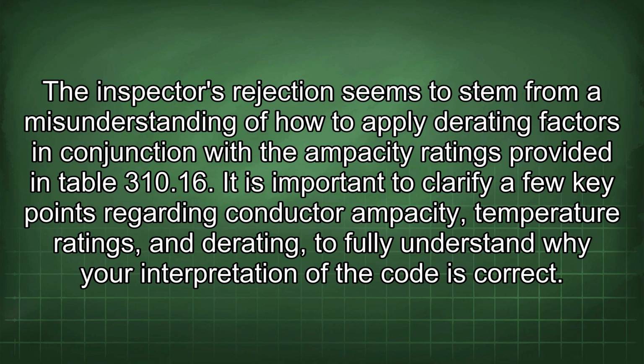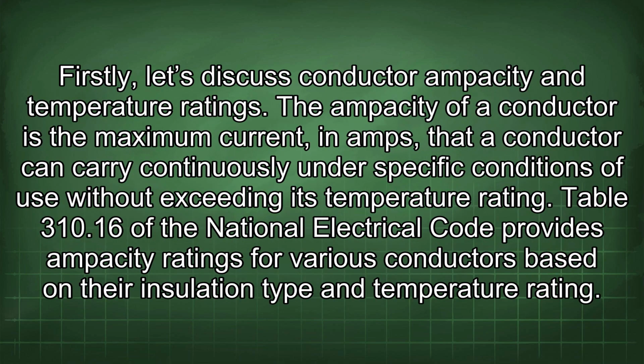It is important to clarify a few key points regarding conductor ampacity, temperature ratings, and derating to fully understand why your interpretation of the code is correct. Firstly, let's discuss conductor ampacity and temperature ratings. The ampacity of a conductor is the maximum current, in amps, that a conductor can carry continuously under specific conditions of use without exceeding its temperature rating.